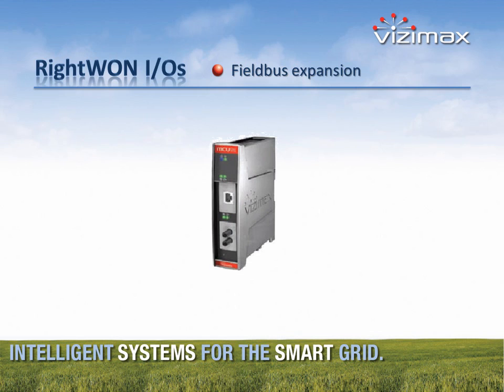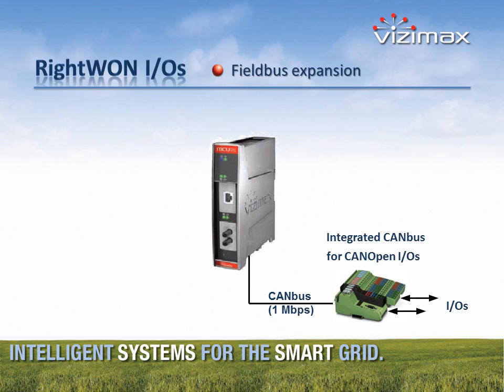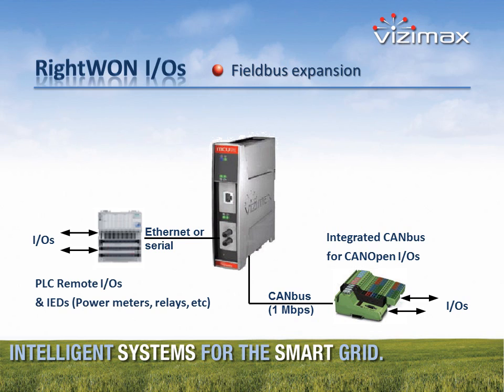Besides the integrated I/Os, the RightWON CPU can be extended using the integrated CAN bus interface. On the market, there are various vendors such as Wago, Phoenix, Weidmuller that are offering CANopen I/Os, which can provide interfaces for analog inputs, analog outputs, digital inputs, digital outputs, and even motor drives. So all these I/Os can be used to expand the integrated capabilities of the RightWON product. We can also use Ethernet or serial communication to remote I/O modules, including PLCs or IEDs to acquire different points.